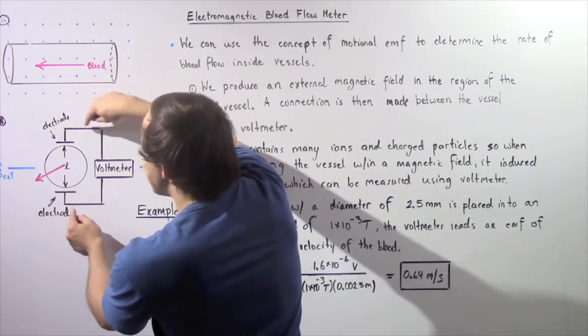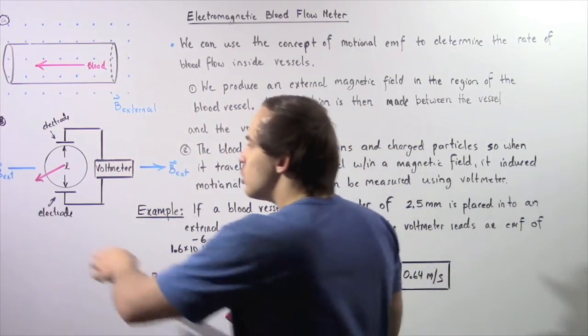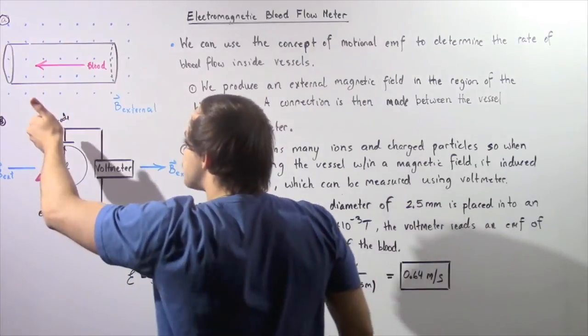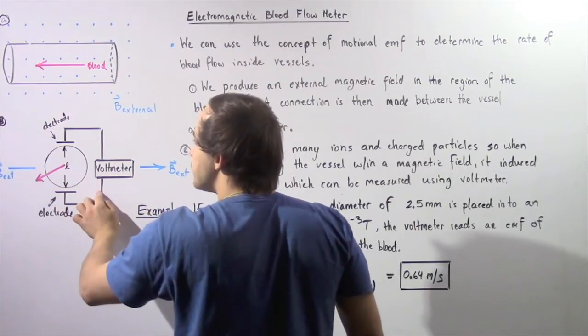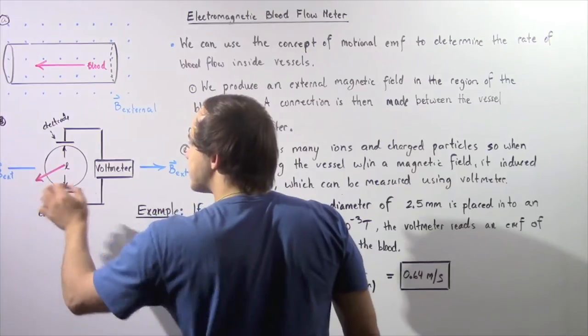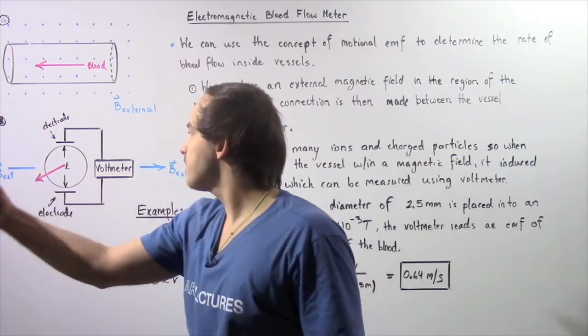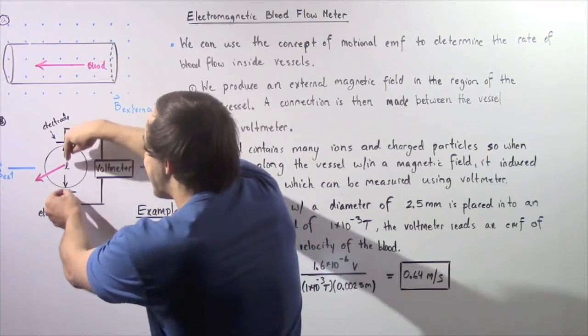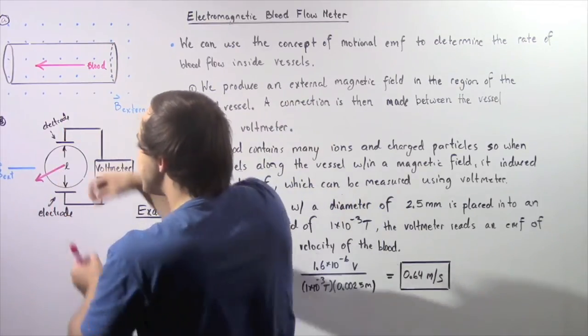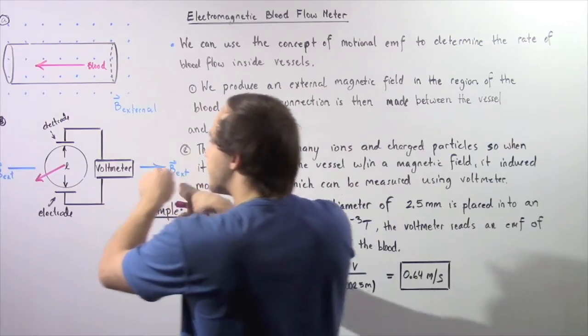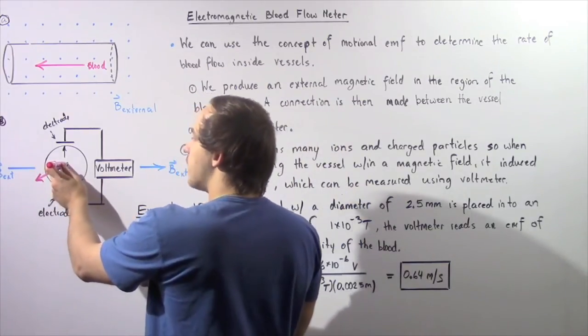We connect these electrodes via a conducting wire to a voltmeter. Notice that we're taking a cross-section area of this diagram, which is what we see in Diagram B. In this case, our magnetic field B points in a general direction and the blood is coming out of the board. The diameter of the blood vessel is given by L, and this diameter L is perpendicular with respect to our magnetic field, which is also perpendicular with respect to our blood flow.